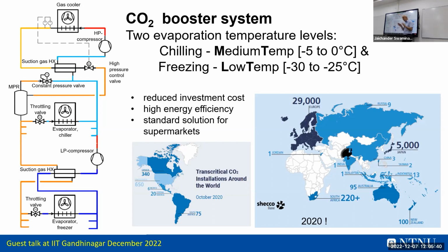With CO2, we are not doing superheat inside the evaporator. That means we don't need to go so low. We can rather spend this surface to provide a uniform temperature, and then we can run very close to the freezing point, meaning many times they don't need to defrost these evaporators, maybe once a week, just for safety. But if you do evaporation around -1 on the fin, there is no freezing. So then the water is running out, it's not freezing. Big advantage if you know how to do it. But this is why you don't do superheating with CO2. Then you get very high suction pressure and high energy efficiency.